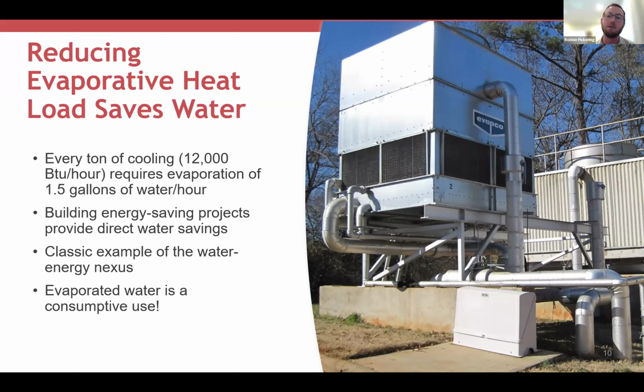The overall cooling load of the cooling tower then determines the total amount of water that's consumed through evaporation over time. We want this cooling to occur. That's the intent of the cooling tower, so evaporation is really not typically the focus of water efficiency. But with that said, anything you can do to make your chiller plant and your cooling tower more energy efficient will also lower your cooling load, which thereby reduces the amount of water needed for evaporation.